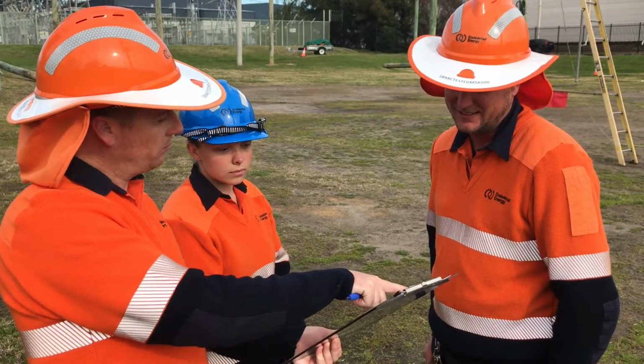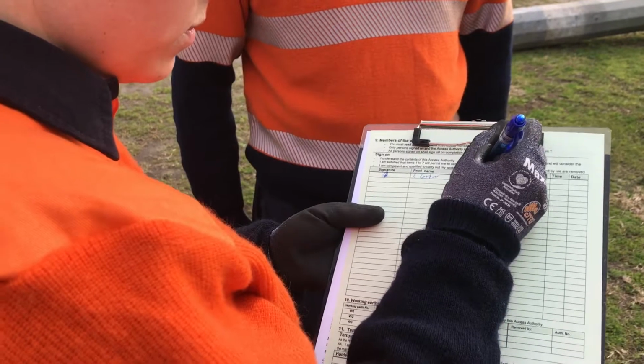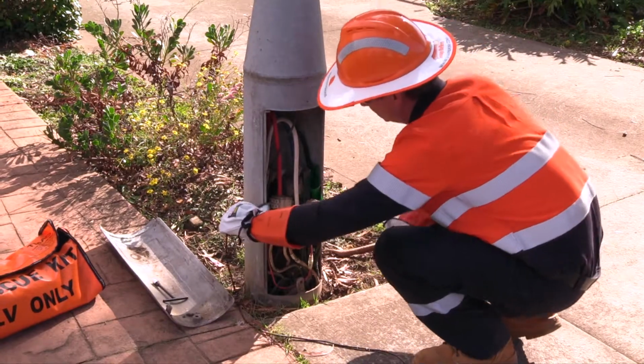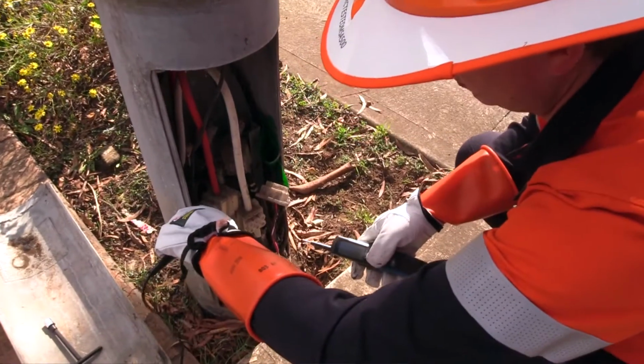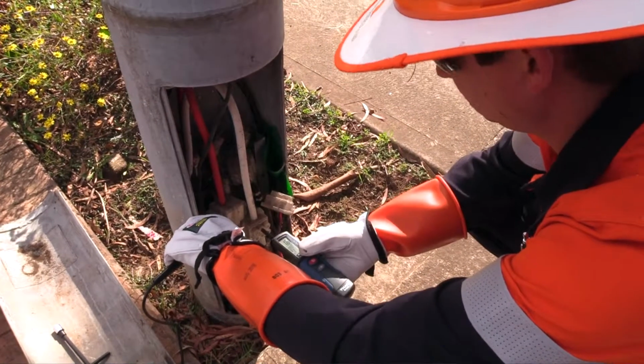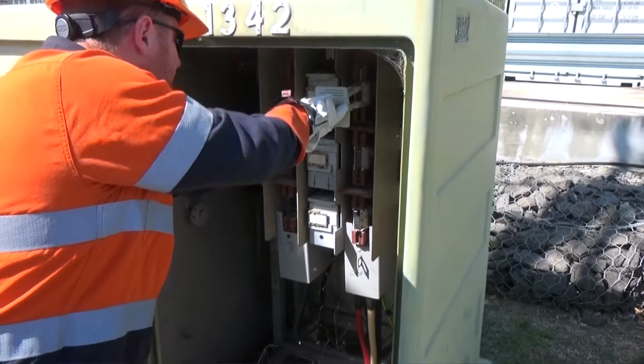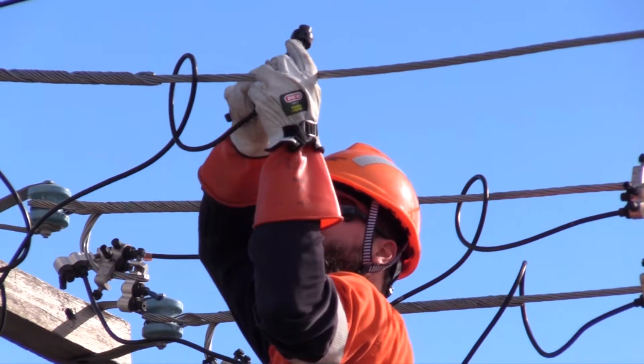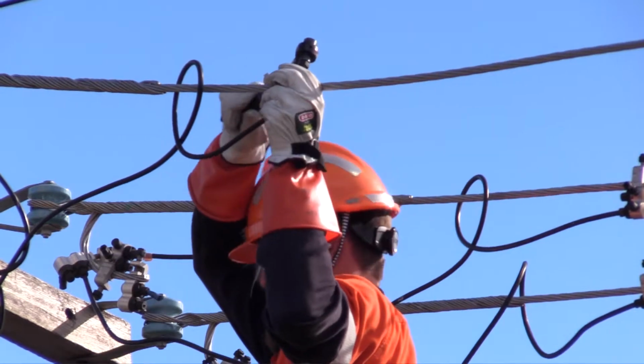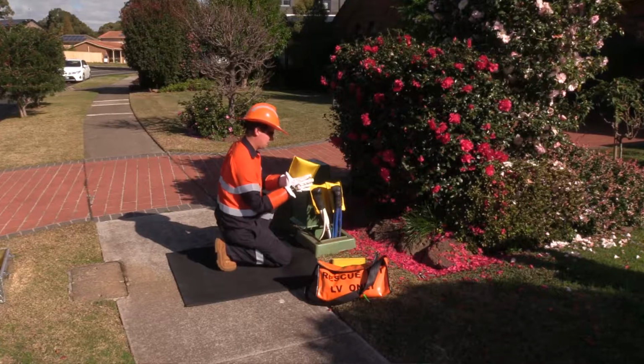Quite simply, if you have not signed on to an access authority for the network apparatus you're working on or near to, you must apply live work controls, even if you're just working near the equipment and not intending to work on it directly. Some live tasks, such as testing to prove de-energised or check phasing, fault finding or applying test equipment, operating switchgear, and making or breaking customer service connections are an integral part of the work of competent authorised electrical trade workers. They still require workers to use appropriate live work control measures though to avoid electric shock or burn injuries.